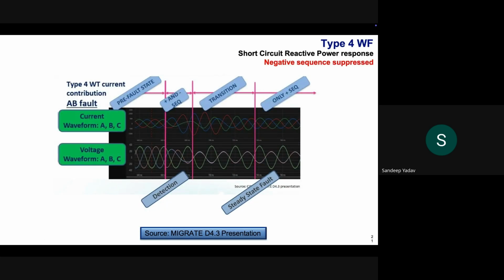So this is a typical fault behavior of a type 4 wind turbine, which is a full converter scheme, not the type 3, which has DFIG, doubly fed induction generator, and where there are two mediums through which the power can go. Type 4 wind turbines are totally decoupled. The WTG is totally decoupled from the grid, and the converters are rated for the full rating of the machine. So if you look for an AB fault or an R2Y fault, in the pre-fault state, there is only positive sequence voltage and positive sequence current in the normal healthy system.